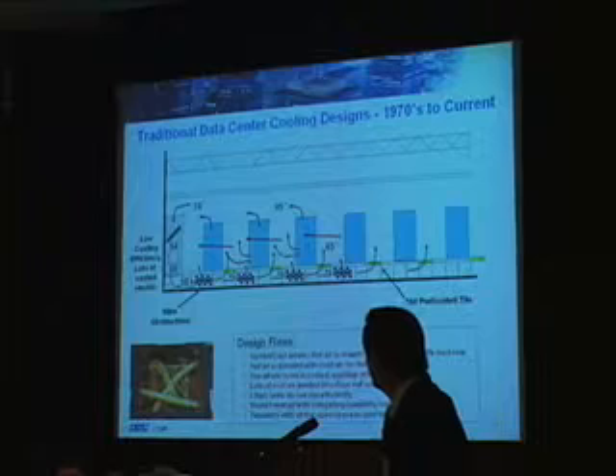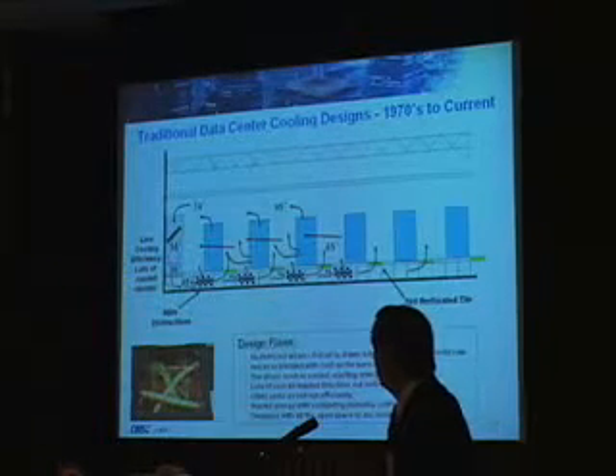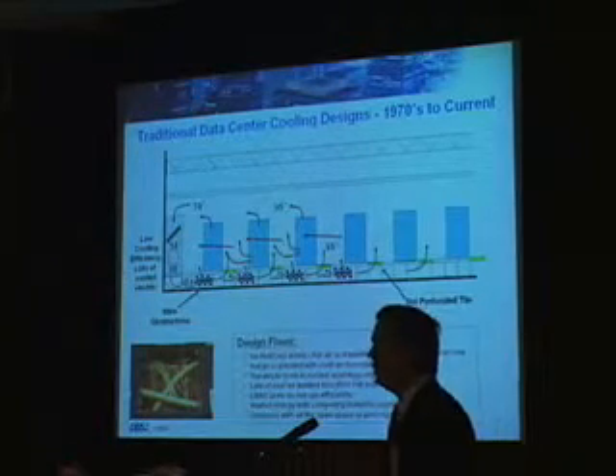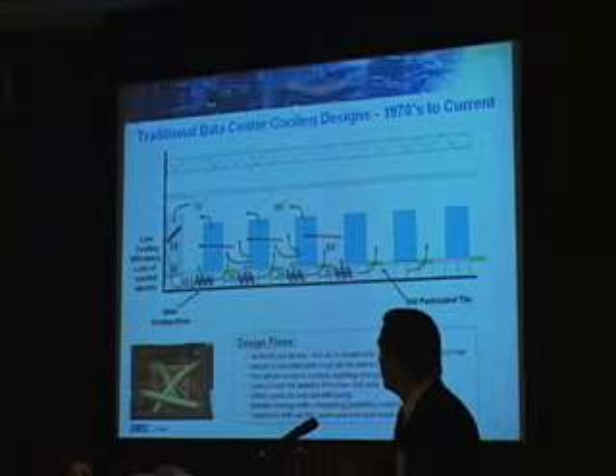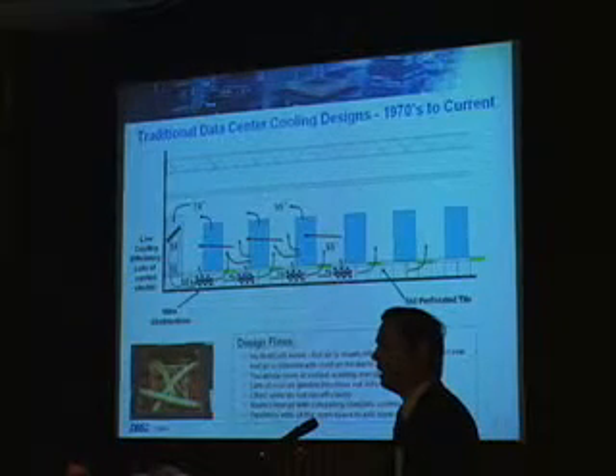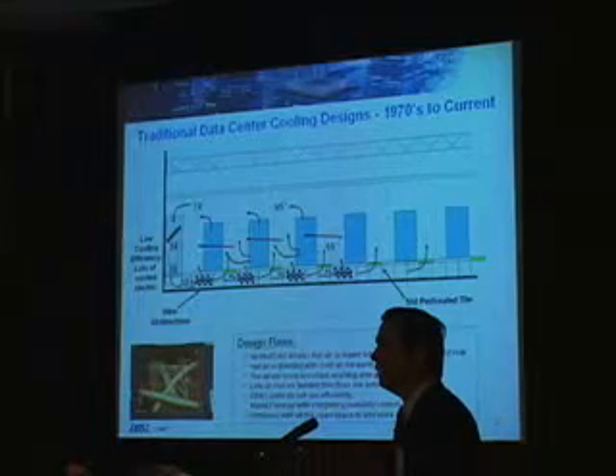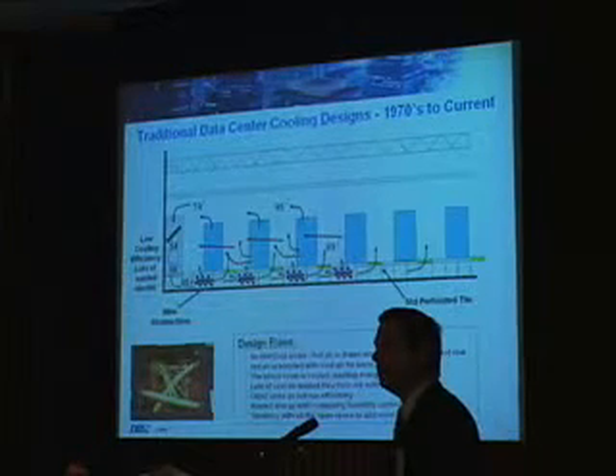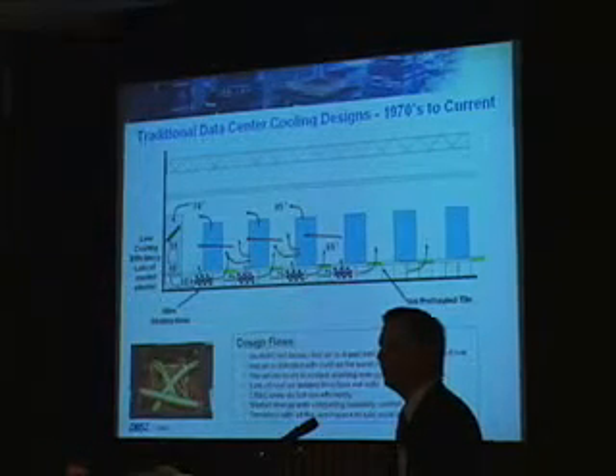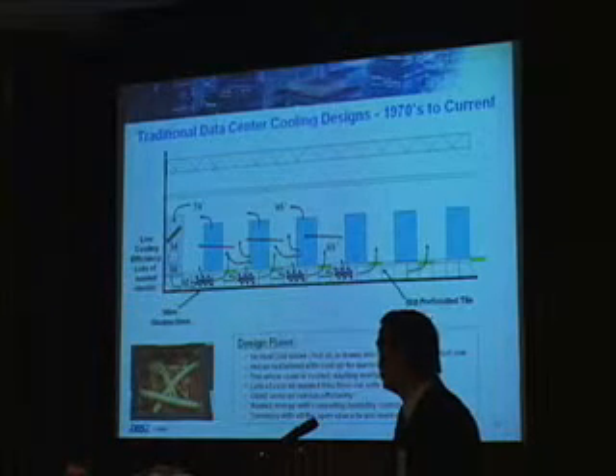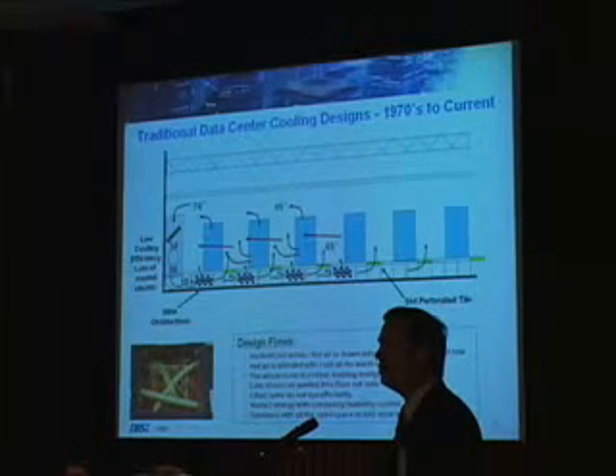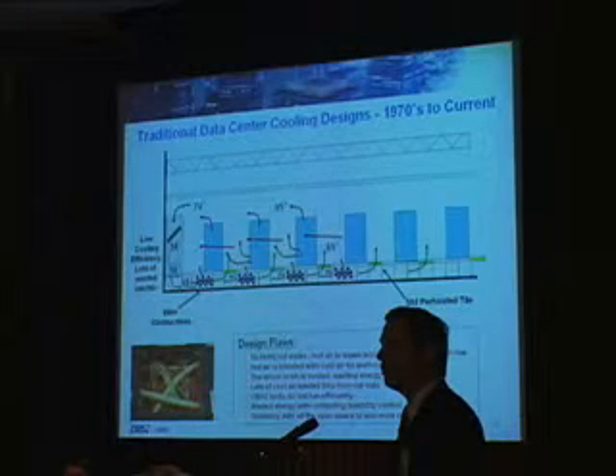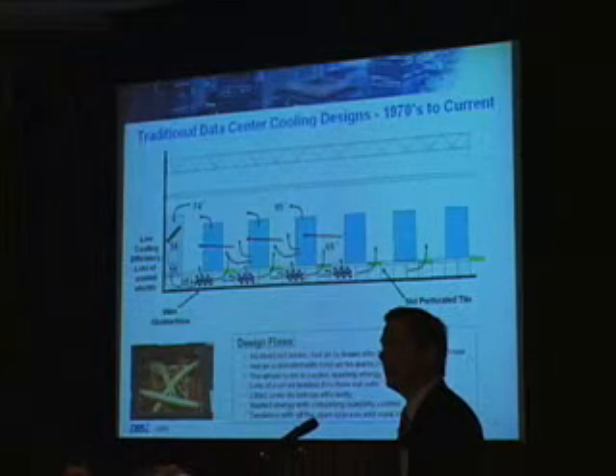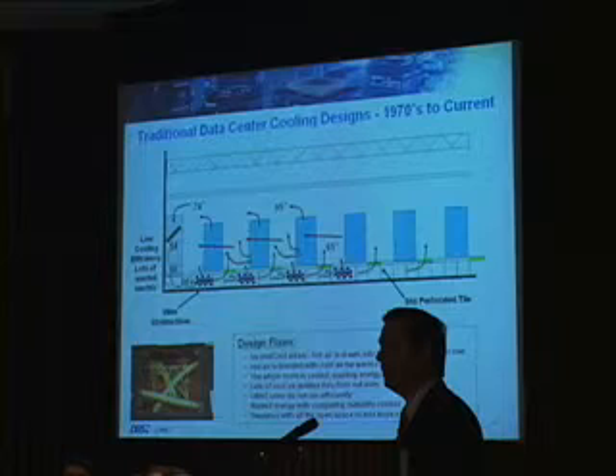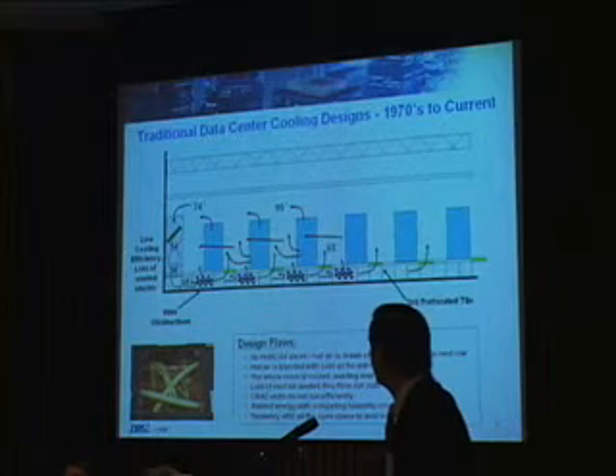With our current traditional data center designs, if you have a raised floor, you typically have your power distribution under the floor, along with your LAN distribution wiring. We go into data centers that had mainframes and they still have their old bus and tag cables abandoned under the floor, taking up space. We talk about energy efficiency, and we're pushing air underneath our floors, but all that cable gets in the way of the efficiency of the air movement, and it actually strangles some of the air movement from getting to the cabinets.